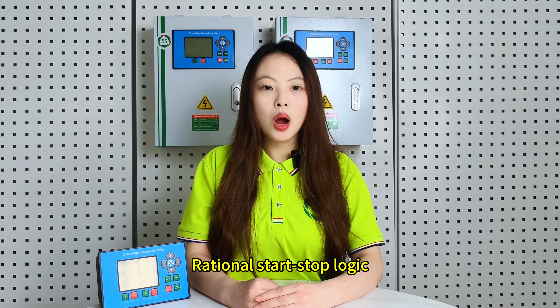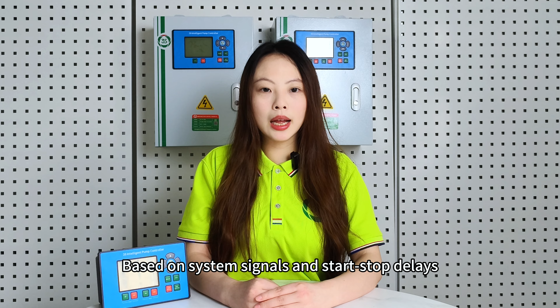Part 3. Core functions of pump controllers. Rational start-stop logic. Based on system signals and start-stop delays, the controller enables automatic operation, reduces frequent actions and unnecessary flow or pressure fluctuations, and better protects pumps and piping components.